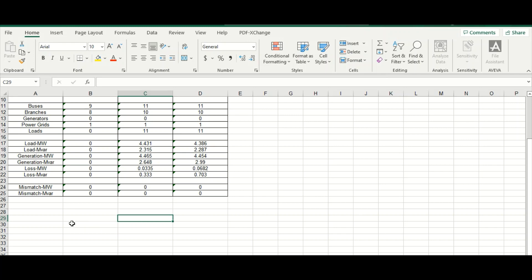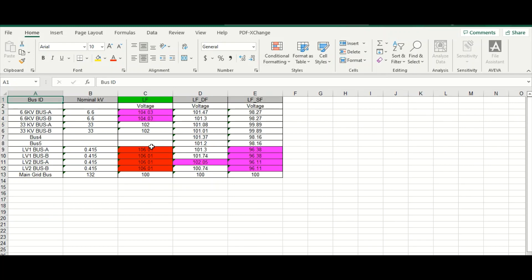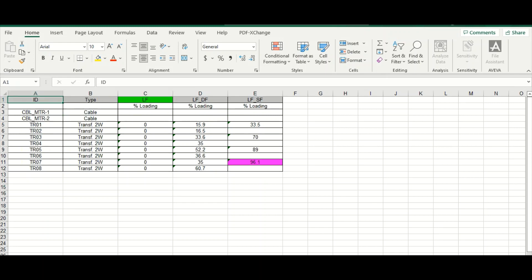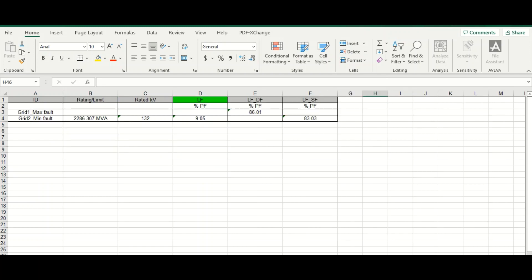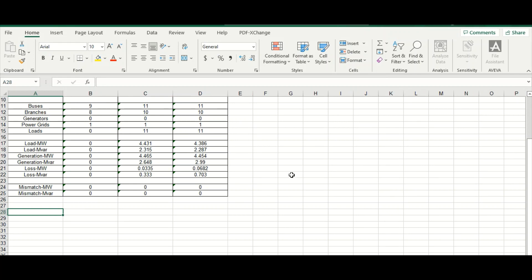If you export this data to an Excel file, you can see all the parameters — general info, bus results with color coding — making it very convenient and easier to understand. Branch results, loads, and sources appear in different tabs in a well-organized way in the Excel spreadsheet. You can customize this data and incorporate it into the main power system study report, which saves time. This is the Load Flow Analyzer.